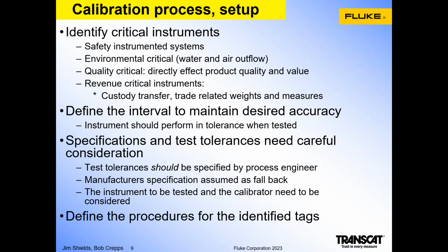Next, once the devices are identified, the interval needs to be defined for the instruments for maintenance to ensure that the desired accuracy is maintained. Ideally, the instrument will perform in tolerance when tested at the end of the interval. And in the event that the device is not within tolerance, that can cause difficulties with some industries. Sometimes that could mean product being scrapped or paperwork to fill out. So ideally, the interval between maintenances and calibration checks is such that the device is in tolerance when tested at that interval. And if not, then maybe that interval would need to be adjusted or shortened.